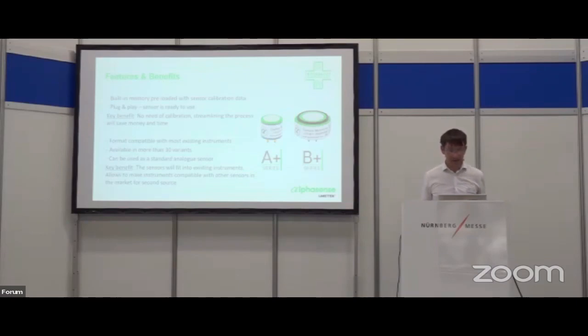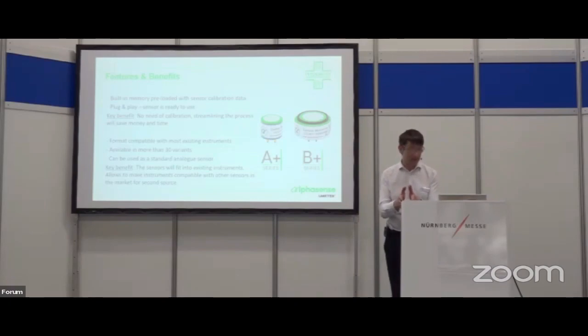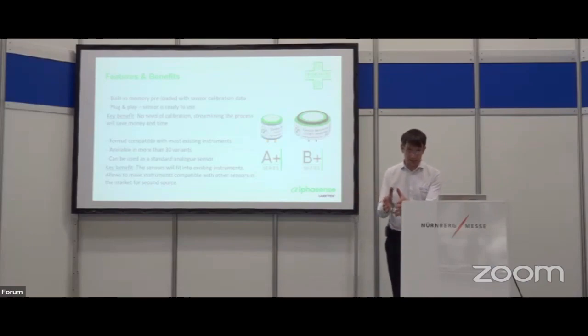Another benefit, coming from the fact that we have a compatible format, is that this sensor can be placed in existing instruments. Maybe the electronics need some changes to read the memory, but the format is the same. It also means that if somebody uses these sensors, they will still be able to use a competitor sensor for second source. They would have to do the full calibration as they do now, but at least it's possible.